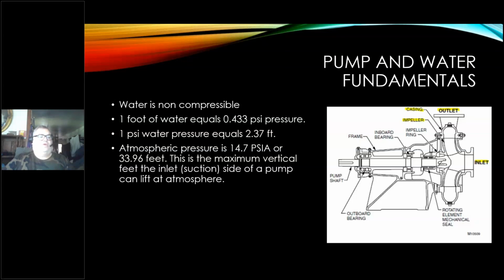If you had a hole that's deeper than that, you had to stage up. You would have to put one pump at the bottom, and then another one 30 more feet up, and then another one 30 more feet up in order to get the water from one to the next. But you cannot pull the water any further than 33.96 feet at atmosphere.